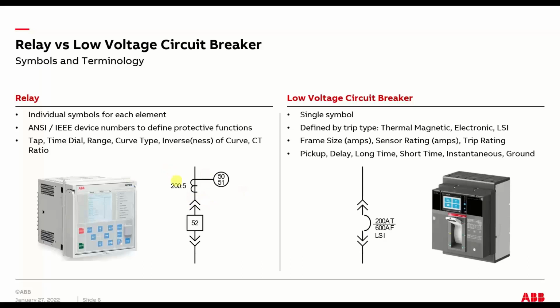Here's real basic stuff: the difference in symbology between describing a medium voltage system and a low voltage system circuit breaker. For medium voltage, the standard ANSI symbol is sort of this box for the breaker, versus this air circuit breaker symbol conventionally used for low voltage molded case and power circuit breakers. The CT is the symbol here, and then the relay.